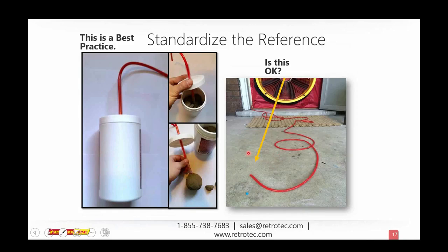Very fastidious, I'm sure, way of testing. In Europe, the maximum pressure that you can test at is 100. The minimum pressure you can test at is 10. And so people think they're supposed to go from 10 to 100. They're not. They're not supposed to go below 10, which means you don't have to go to 10. And you're not supposed to go above 100. Most of the results you're looking for there are at 50 pascals. You'd probably get better results if you tested from 40 to 60 pascals than going over that wide range.